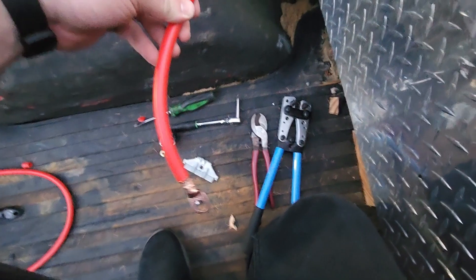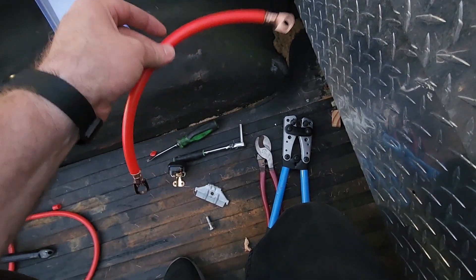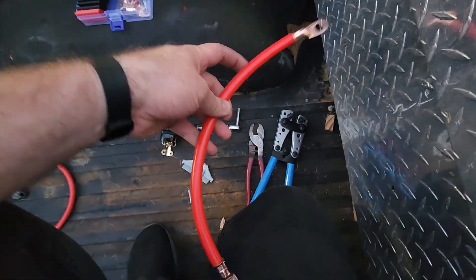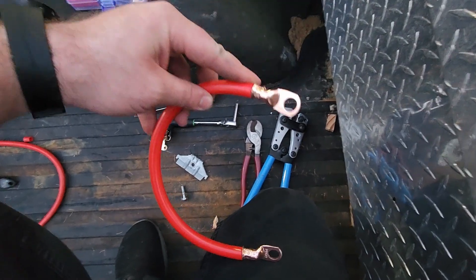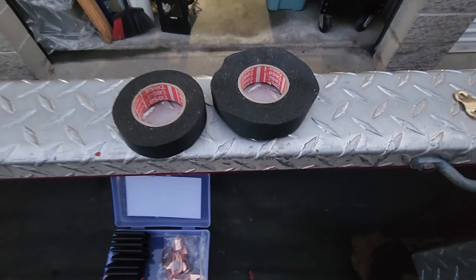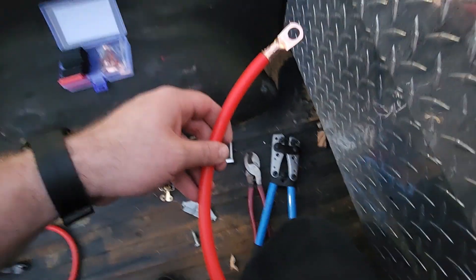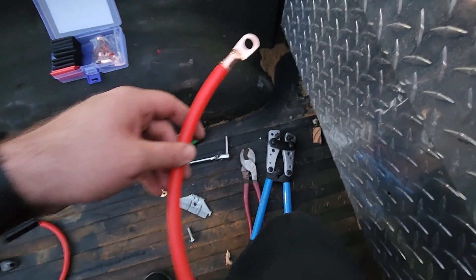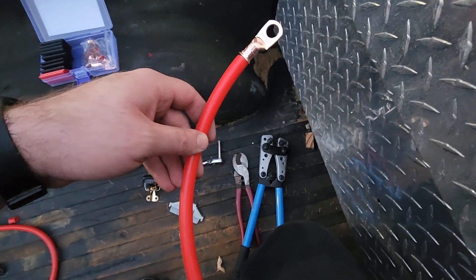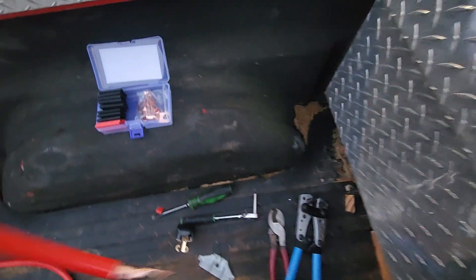One thing I like to do: after you strip and crimp, whatever curve the wire has naturally I don't like to fight that. So I'm just arcing it over from one terminal to the other. I'm going to wrap it with Tesa tape just to cover up the red — there's no point buying black wire if you're just going to cover it. Whether you're using electrical tape or Tesa tape, I wrap it and then go over it with a piece of heat shrink tubing.